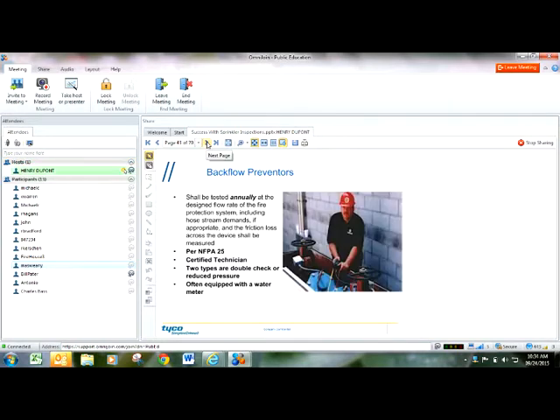Backflow preventers are required to be tested annually, and they have to be done by certified technicians, not qualified technicians, but certified technicians. A lot of plumbers are certified. Fire life safety companies are certified. And what we do is we find that a lot of plumbers will inspect our fire backflows, and we do a lot of inspections on other backflows in the facilities, not just the fire sprinkler ones, but they have to be tested annually by certified personnel.